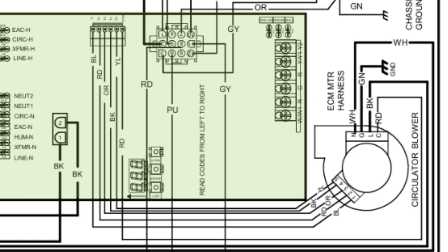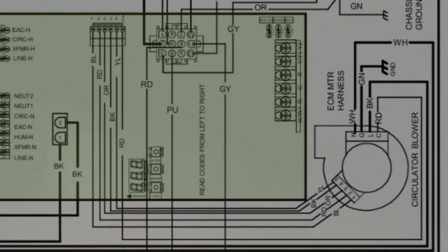When you understand how control boards use series wiring and parallel wiring, and then you overlay the sequence of operations on top of that, it becomes very, very clear where you need to test the control board and when you need to test it there to see if the control board is actually doing what it's supposed to be doing and whether or not it's time to condemn it.